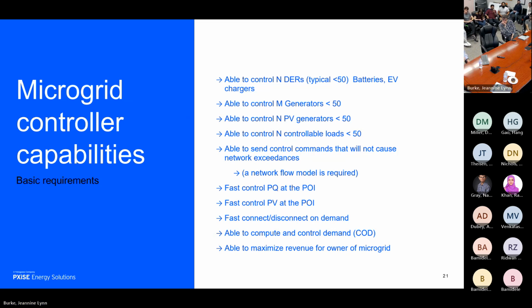Now, I wanted to summarize what we think a standard microgrid is. There should be one piece of software that is the microgrid controller. That piece of software should be configurable so it will control a number of inverters, a number of batteries, a number of PV generators, a number of controllable loads. It cannot send any commands to a controllable device that will cause a network exceedance. Otherwise, the owner is going to get upset because you tripped off some equipment because you sent too big a P command to an inverter. So every command that's sent needs to be checked for thermal and voltage constraints inside this microgrid.